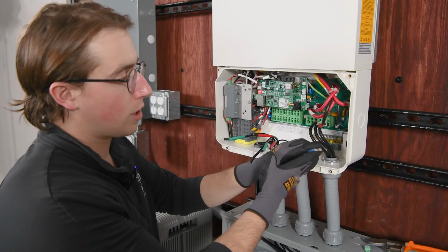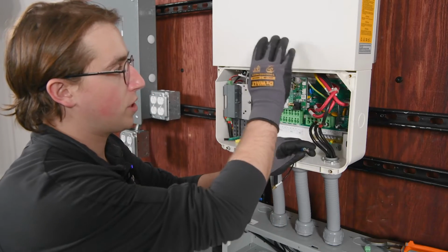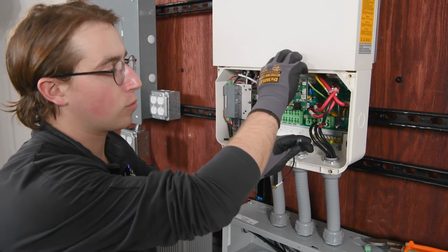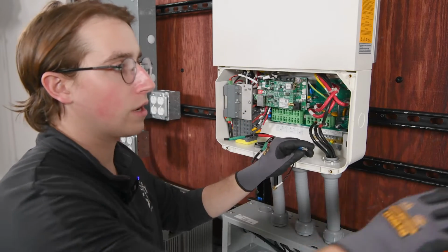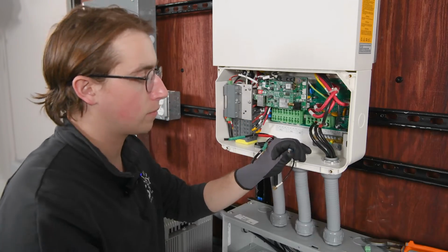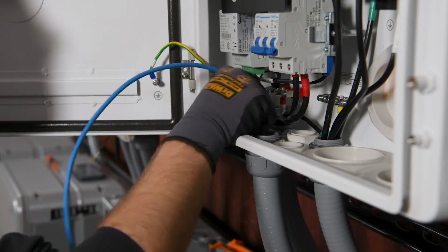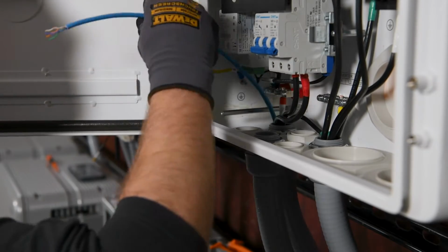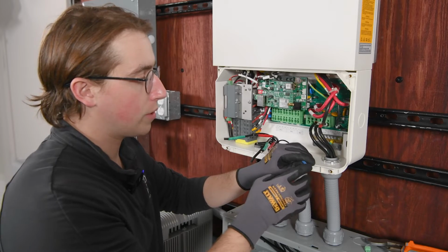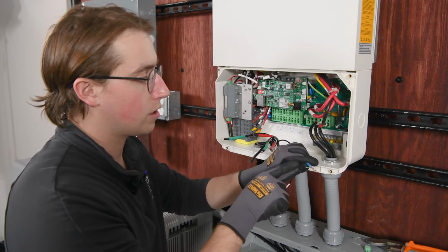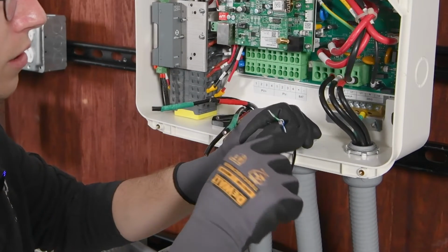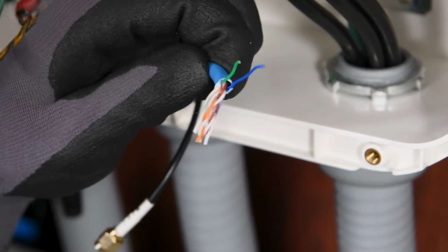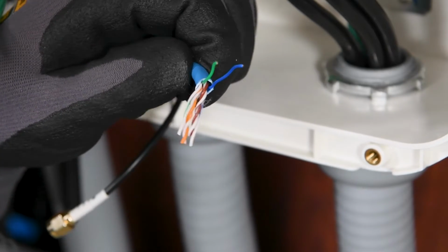So now we're setting up communications between the MIN 11.4 hybrid inverter and the Growatt SYN. For this connection, we'll be utilizing a standard Cat5 or Cat6 Ethernet cable. And what we'll be doing here is we'll be taking the green wire and the blue wire to set up communications. So we'll show you how to do that right now.